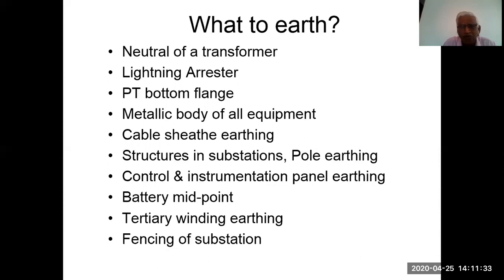Battery midpoint is also earthed to find out in case there is any problem with the DC supply cable, if the cable is being damaged or something like that. And tertiary winding, in case you have seen ICT transformers, interconnecting transformers between 400 kV and 220 kV. They are all auto transformers. They are called ICT, and they will have a tertiary winding. The tertiary winding has to be grounded, but the manufacturer always tells you whether it has to be earthed or not. Based on that, follow the instruction. If no instructions are given, you can earth one terminal of that. Now, fencing of the substation also we have to earth.